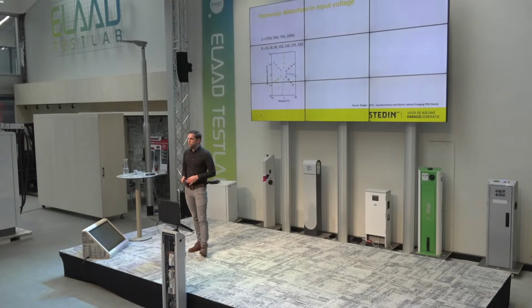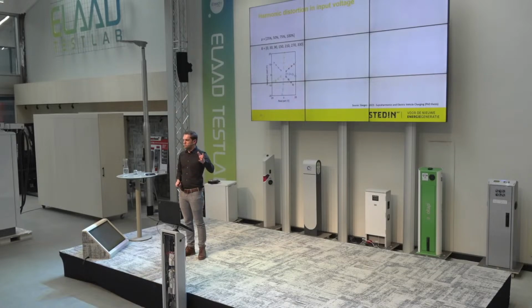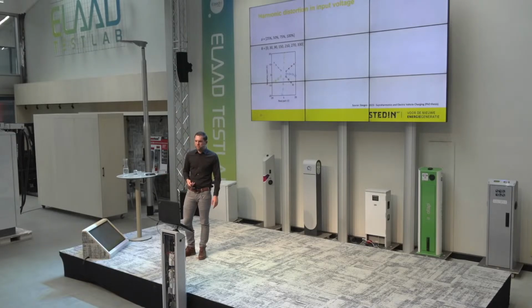If we have a device, for instance an electric vehicle charger, we have many of them, and we connect them here to the network and measure what the emission will be, we get a result, so we know what the emission is. Let's put it in the field, everything is within the limits. But if we then put the charger in the field, the emission you get from it might be totally different, and this has to do with the fact that the emission also depends on what voltage you put into it.